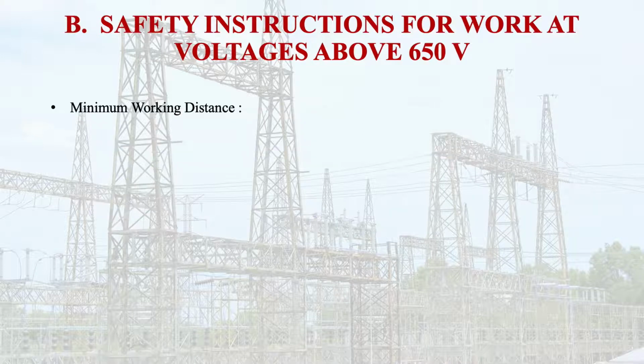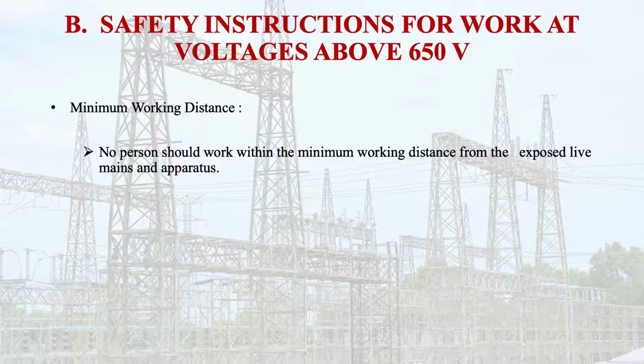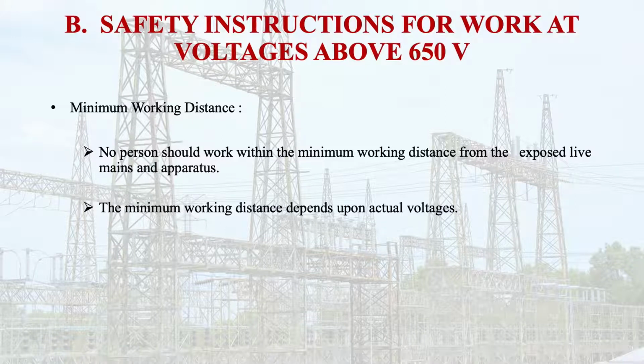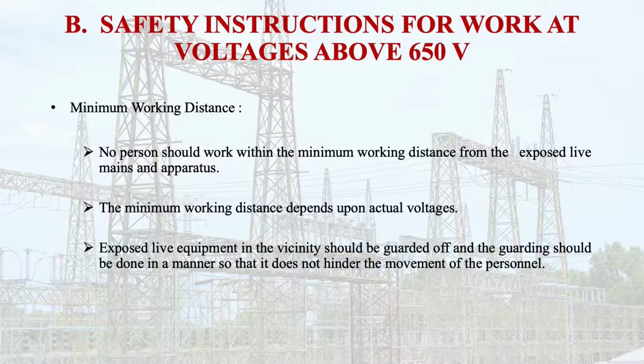Then, minimum working distance while working on high voltages. No person should go within the minimum working distance from the exposed live mains and apparatus. The minimum working distance depends upon the actual voltages. Exposed live equipment in the vicinity should be guarded off, and the guarding should be done in a manner so that it does not hinder the movement of personnel. If necessary, a person for observing safety could be posted.